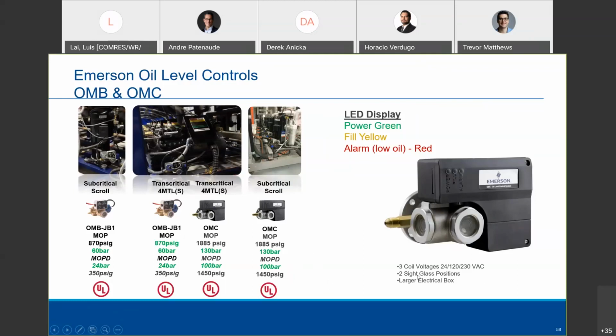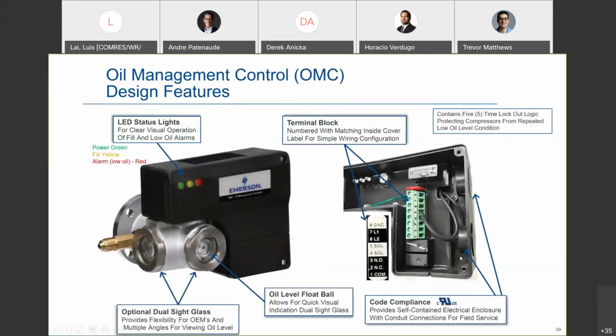And there's 3 voltages. That's a new feature: 24, 120, and 230 volt. And there's 2 types of models. One has a double sight glass here, so it's easier for viewing from a contractor perspective. And there's another model that just has the 1 sight glass. Just kind of a look at the inside. There's a Hall effect magnet like the OMB, to keep the float from being jammed up with metal particulates, because the magnet is not in the oil space. So that's an advantage, of course.